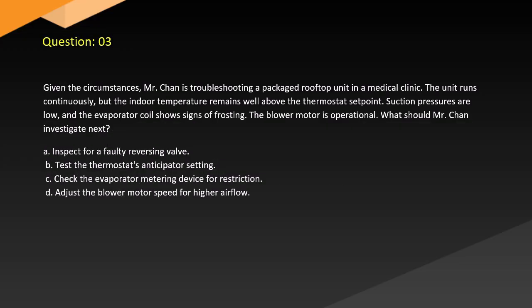Question 3. Given the circumstances, Mr. Chan is troubleshooting a packaged rooftop unit in a medical clinic. The unit runs continuously, but the indoor temperature remains well above the thermostat set point. Suction pressures are low, and the evaporator coil shows signs of frosting. The blower motor is operational. What should Mr. Chan investigate next?